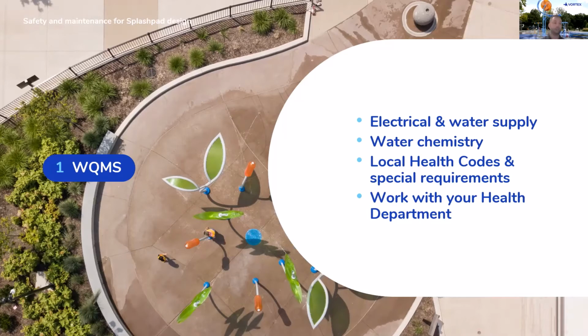On the other end of the spectrum, the WQMS equipment that shows up on site will be tailored to the electric supply. So knowing the phase information, whether it's single phase or 3-phase, is going to be crucial. Very simple, hey, what's the electrical supply you have on hand, but it's very, very crucial. Again, those pumps are either going to be designed for 3-phase or single phase. If they're designed for 3-phase, we can't go back to single phase, and that'll really slow things down.